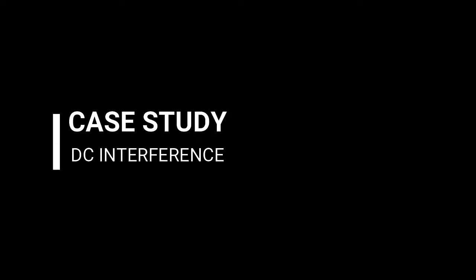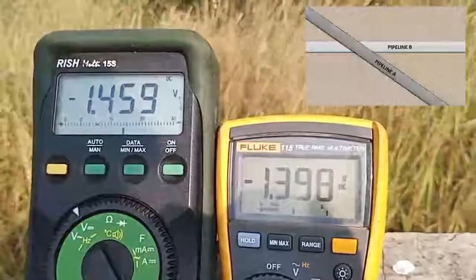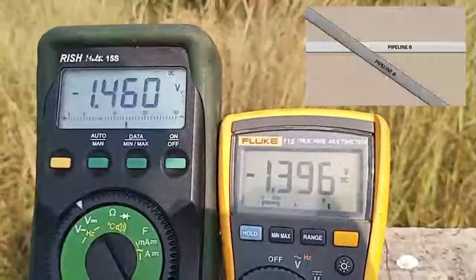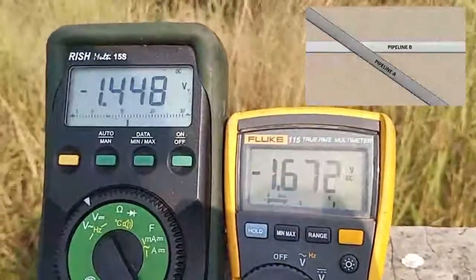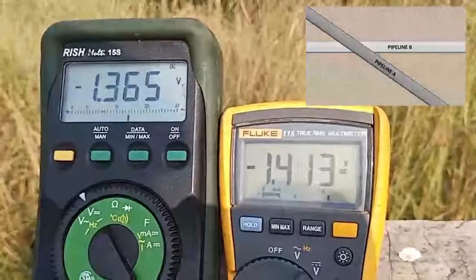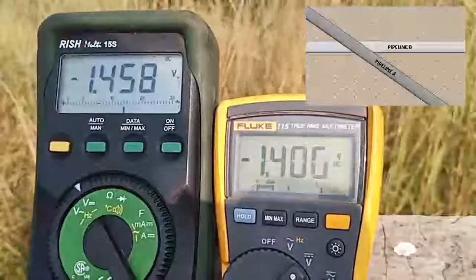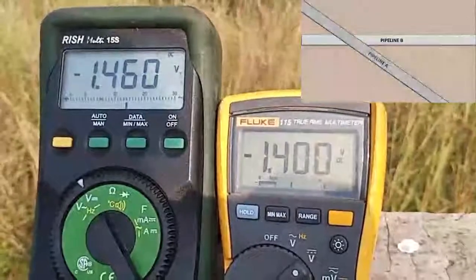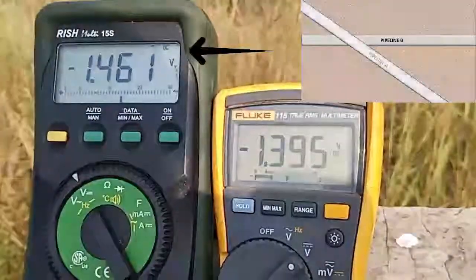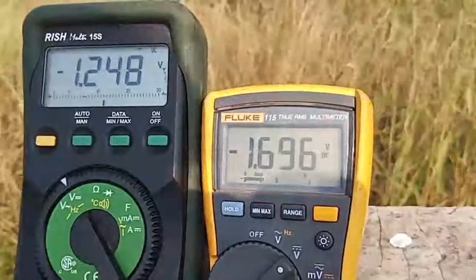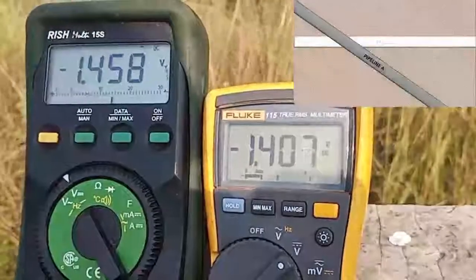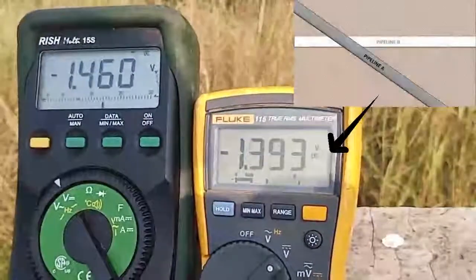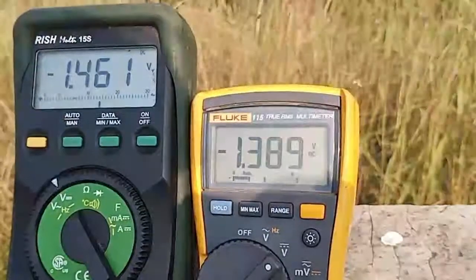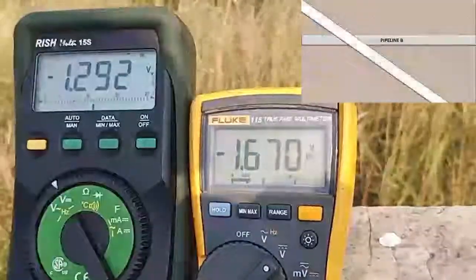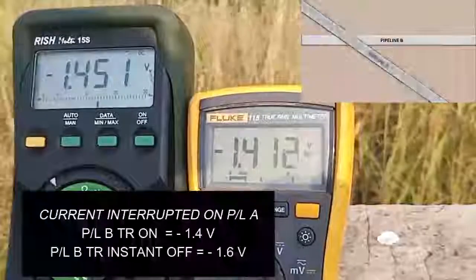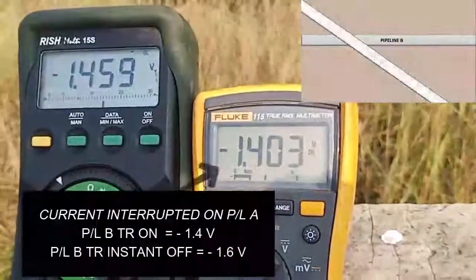This is a case study involving two pipelines, Pipeline A and Pipeline B. As you can see in the diagram, Pipeline A is crossing Pipeline B. The black multimeter is measuring the potential of Pipeline A and the yellow multimeter is measuring the potential of Pipeline B. When the TR unit of Pipeline A is interrupted, we get the following readings on Pipeline B.